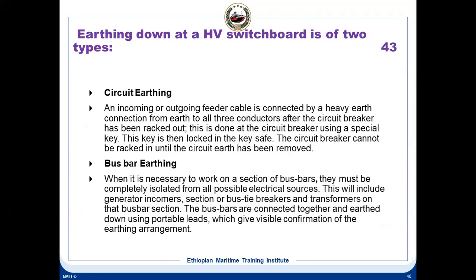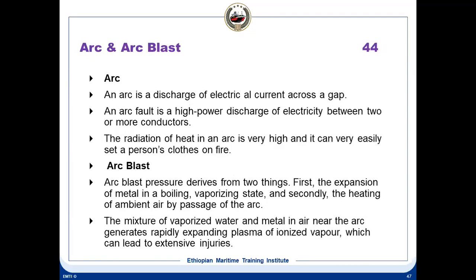Earthing, what is earthing? What is circuit earthing? What are the types of earthing? Circuit earthing, bus bar earthing. The difference between circuit earthing and bus bar earthing. Circuit earthing means it has an inbuilt earthing switch. Bus bar earthing means you use portable earthing cables to connect for grounding. Okay, this we have discussed.